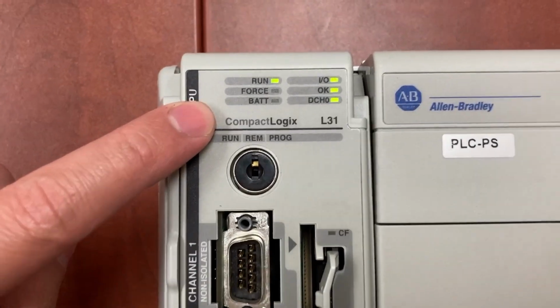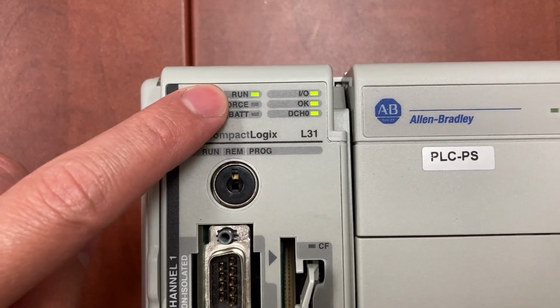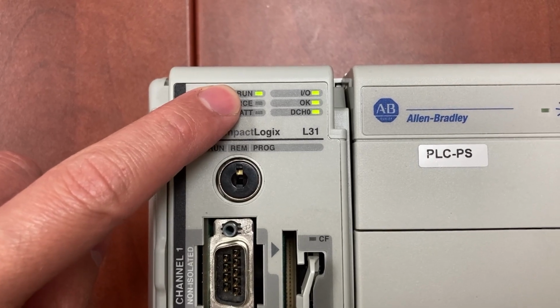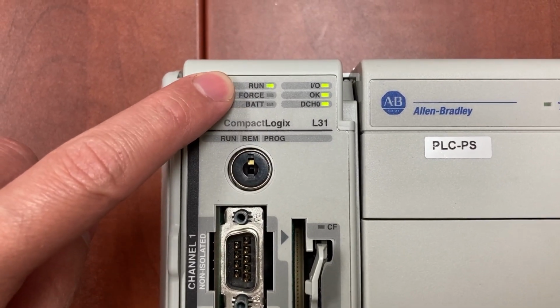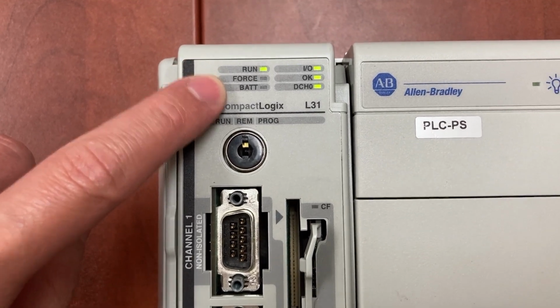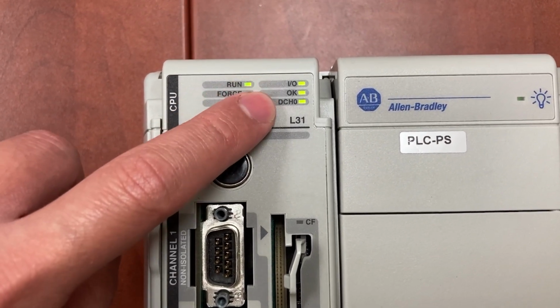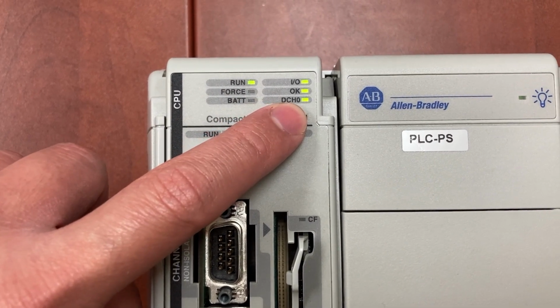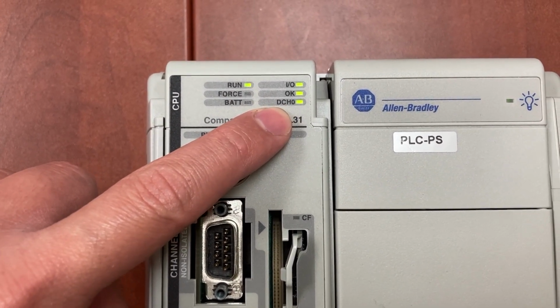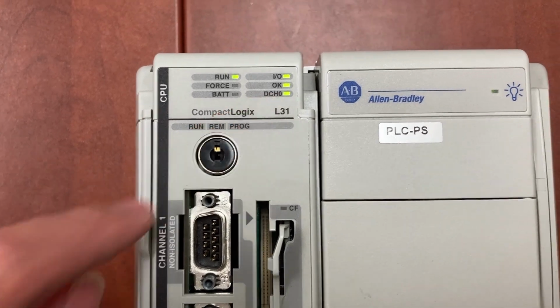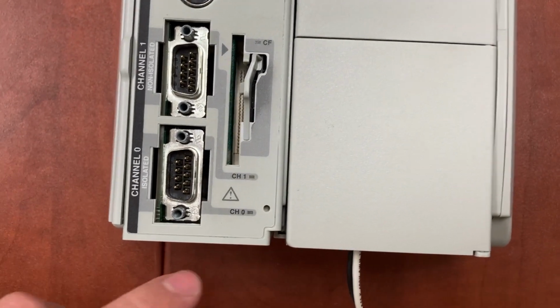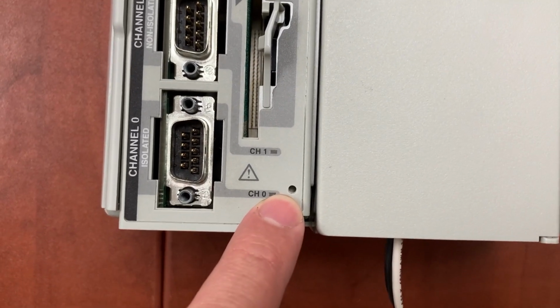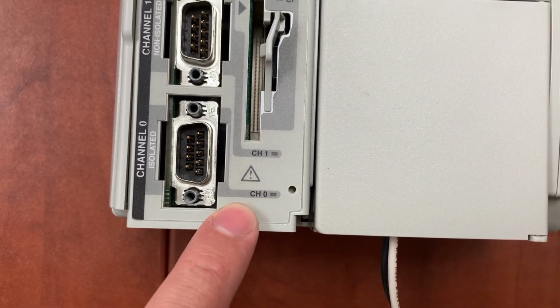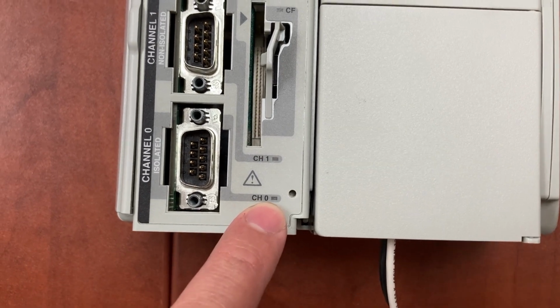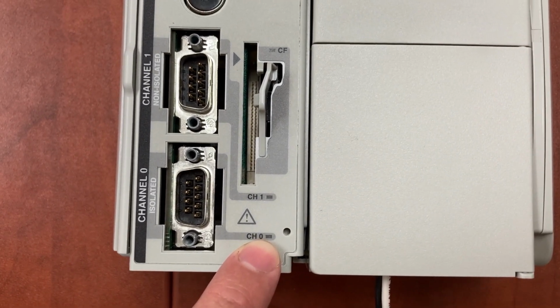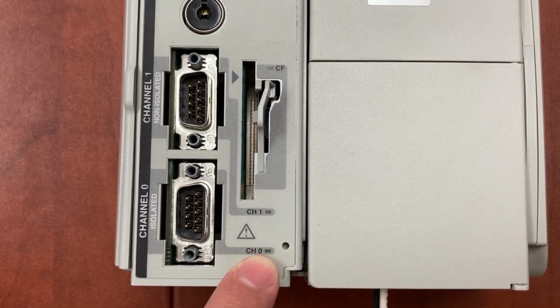On the front of the PLC, there are 6 little LED indicators for the controller statuses: run, force, battery, IO, OK, DCH0, that means default communication channel 0. It also has a little hole for a push button to default channel 0 back to the default serial communication, which is DF1 full duplex.